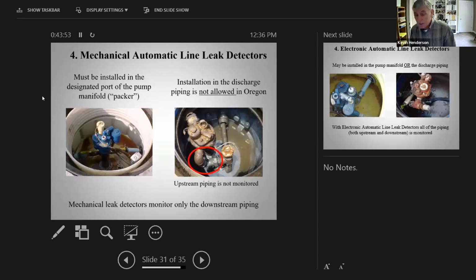One of the things that we still see a lot of is this. In the old days, there were certain submersible pump manufacturers who did not build their pump manifolds, the pump head, the packer, whatever you want to call it. There was no place to install a leak detector in those old pump heads. Most of the ones that are left are Tokheim, first generation Tokheim STPs. There was no place to put a leak detector in. And so they came out with these special T's, these machined T's that have a signaling face on them. That's what you see in the right picture. The leak detector is actually installed in this T off to the side of the submersible pump.